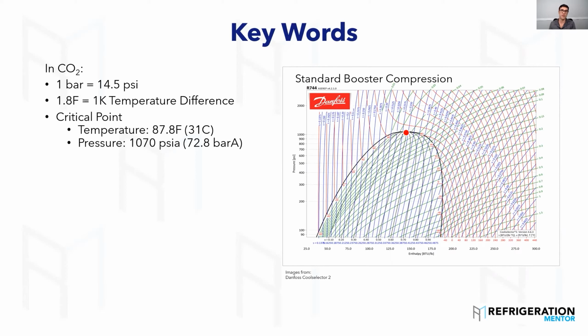But newer synthetic refrigerants were easy to use, lower pressure, and we went through a cycle of having synthetic refrigerants. Now we're back in natural refrigerants. You're going to start seeing them heavy. Regulations are pushing CO2 or natural refrigerants. You're going to see more CO2. You're going to see more propane. You're going to see low GWP refrigerants, by which I mean global warming potential, like A2Ls, which are mildly flammable refrigerants. If you have not seen them already, you're going to start. There's going to be a massive influx of CO2 equipment in the next 10 years. There's already a lot, especially here in North America and around the world. You're going to see a lot more.